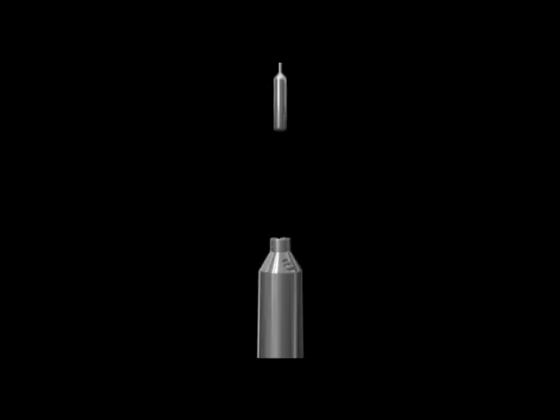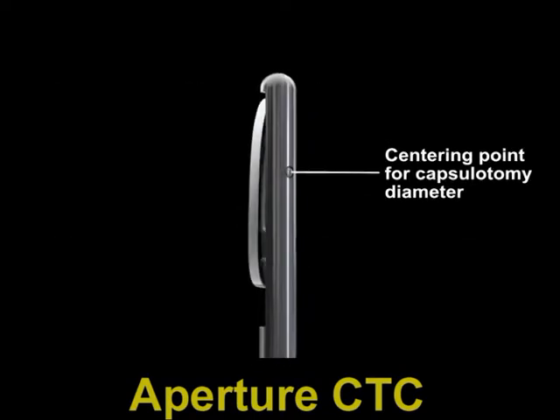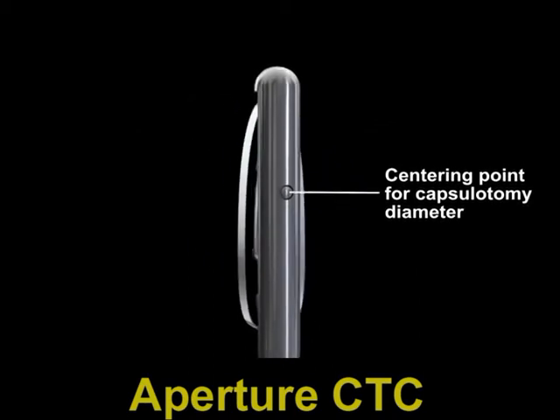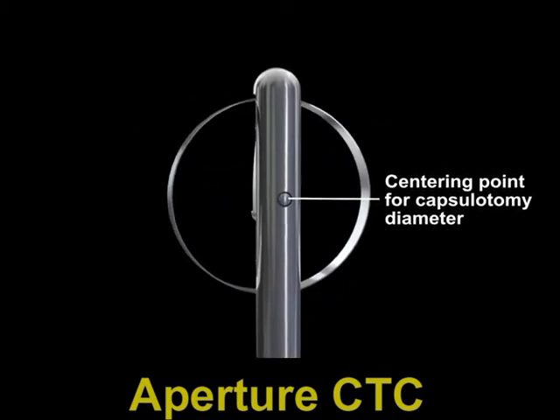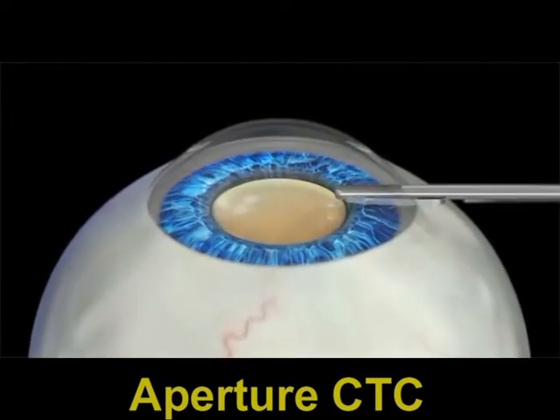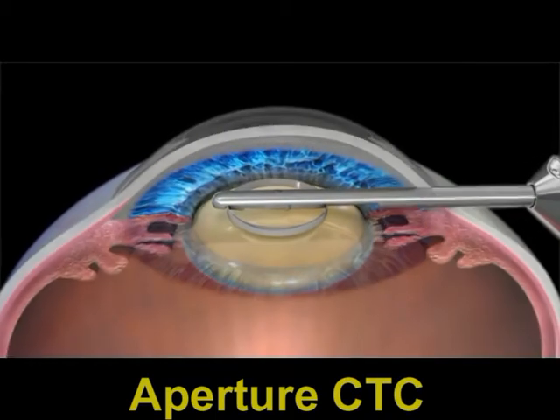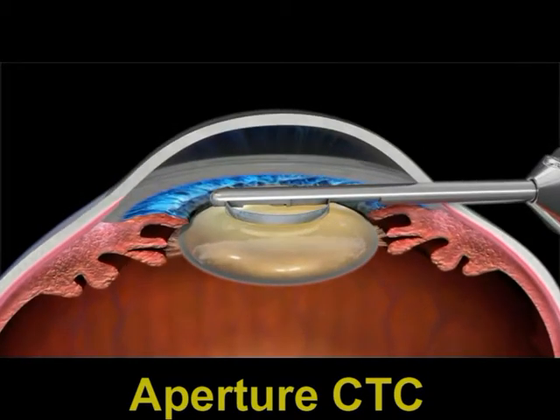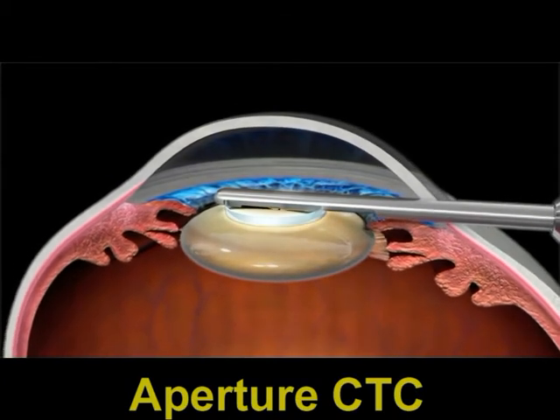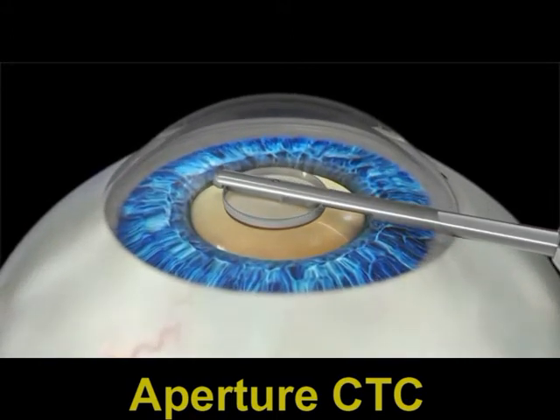The other device in the pipeline is the aperture CTC, which has tips of various sizes. This is the tip and the centering point for aligning the capsulotomy diameter. The aperture CTC, or continuous thermal capsulotomy, works through a steel ring and is a non-laser-based system. Continuous controlled low-level energy is provided to the cutting elements on the steel ring, creating a smooth, repeatable, uniform capsulotomy.